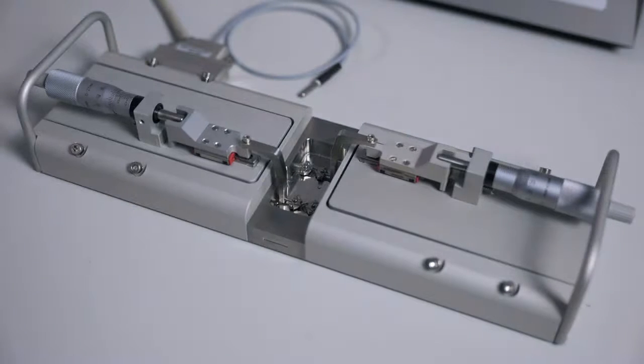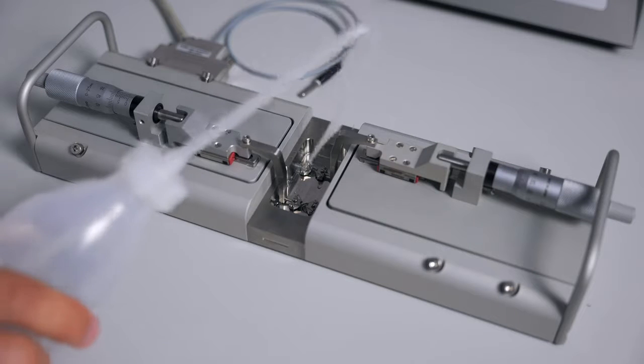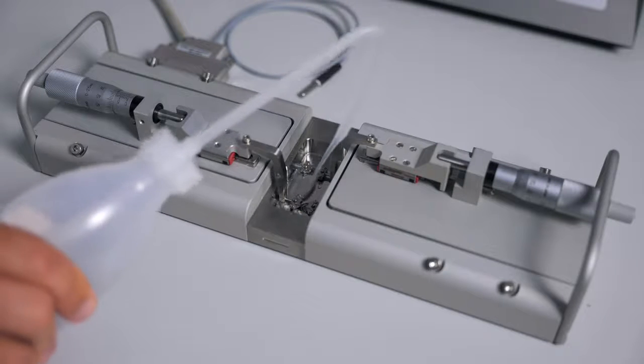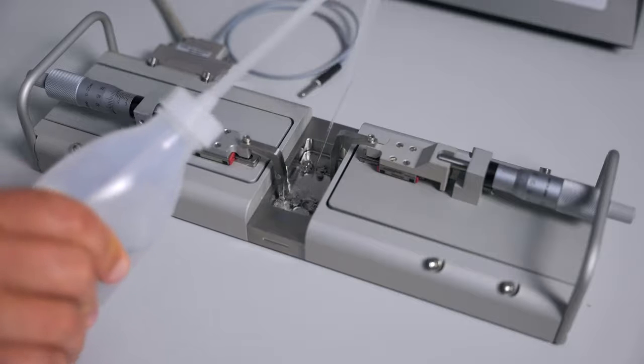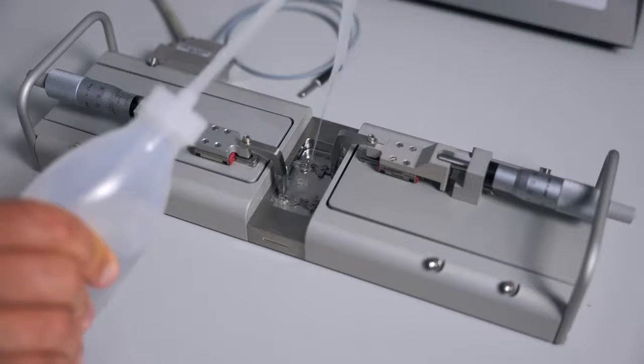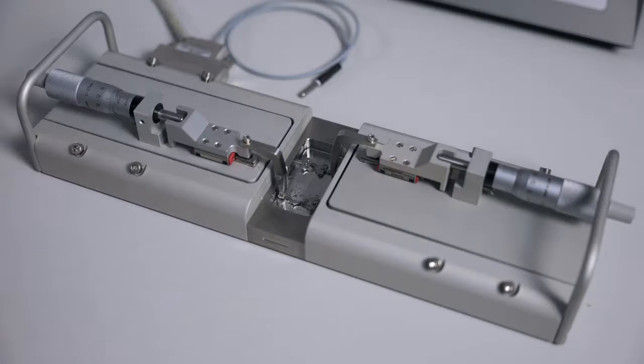If a hydrophobic reagent was used, the daily cleaning procedures might not be strong enough to properly clean your chamber. You can use 96% ethanol or a weak detergent solution. To clean more resistant or toxic chemicals, you can fill the chamber with 1 molar hydrochloric acid for 1 to 2 minutes and let that soak.